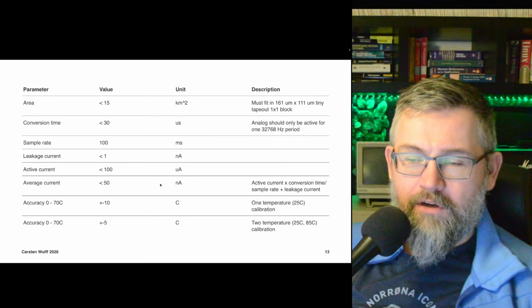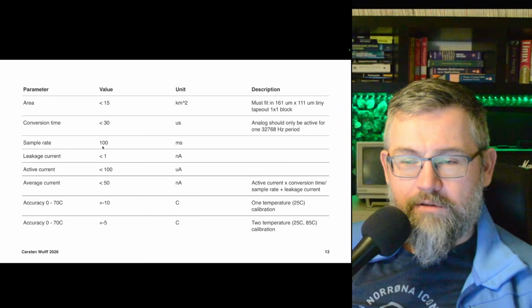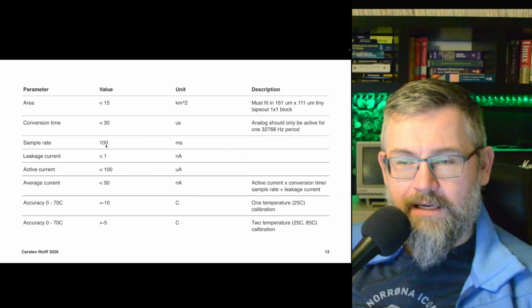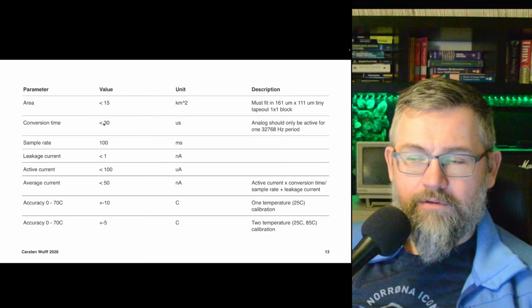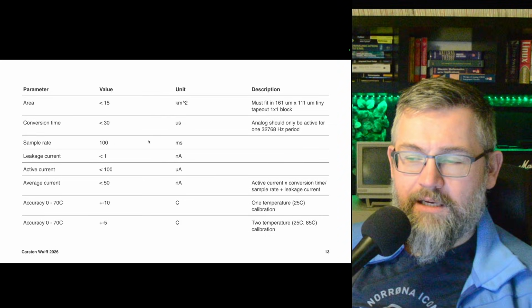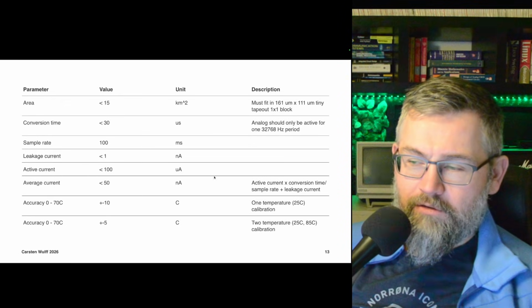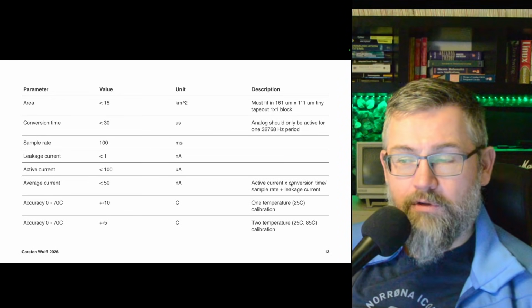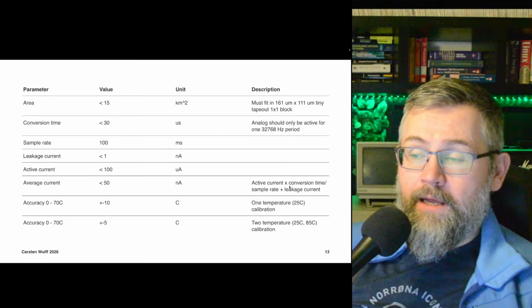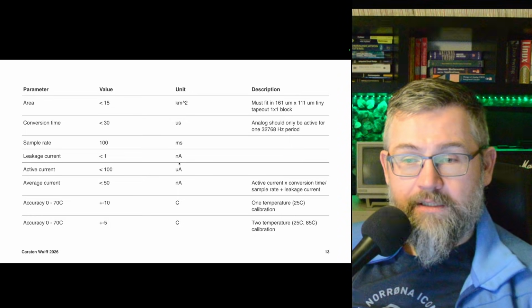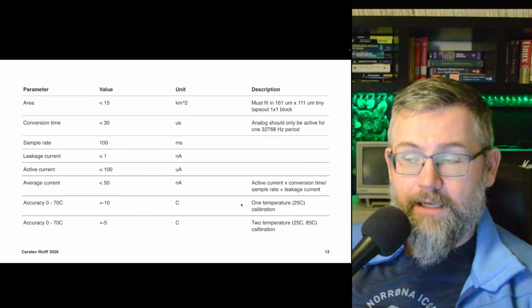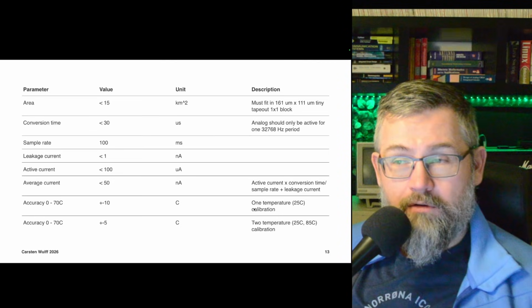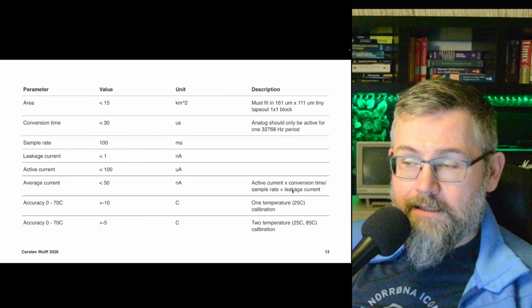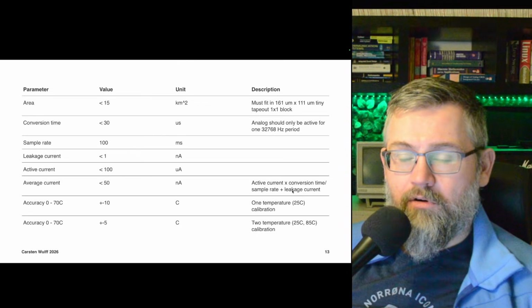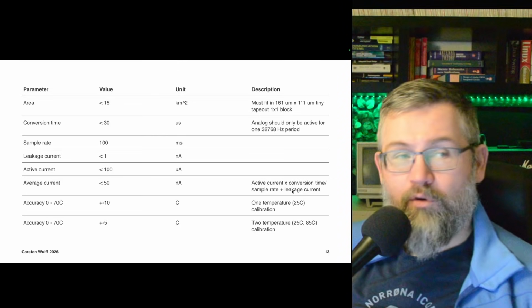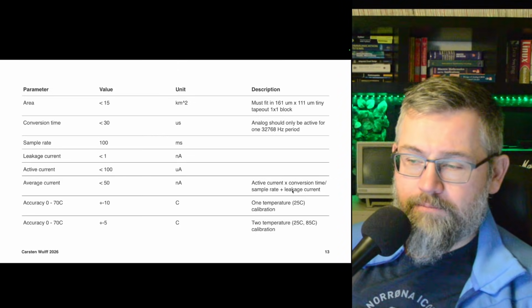And the average current, well, if we sample once every 100 milliseconds, and the conversion time is 30 microseconds, then we can take the active current, multiply that by the conversion time to get actually charge, and then divide that by the sample period, which is 100 milliseconds, to get back to the average current over that interval. And then we can add the leakage current. And that gives us a good measure of the performance of the temperature sensor.